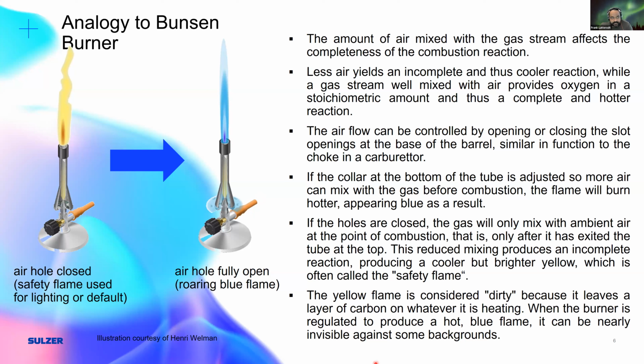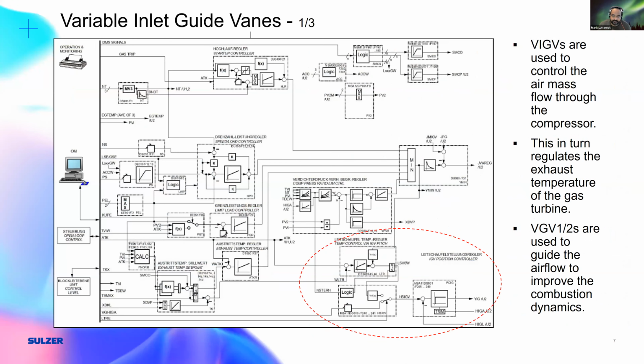Now, this is the analogy. I want to show you what the concept looks like. So this is a simplified overview of what the gas turbine control philosophy looks like. You have inputs that are communicated to, let's say, a central control room or a main control room. I think those familiar with the KKS system would know this as the UBA building, where all the cables coming from the field, measuring speed, temperature, electrical output, the temperature of your gas, if you are running on gas or oil, all these commands are coming in also from your boiler.